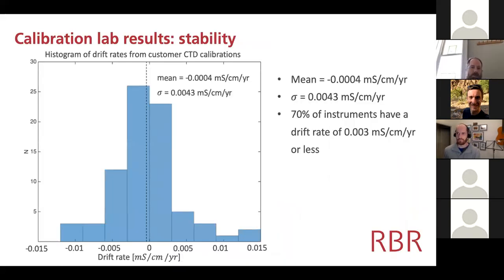Long-term stability. So we took a group of, I don't know, I think it was about 100 instruments maybe. And they had come back from calibration from users who had had them all over the world in completely unknown conditions. We had no idea how long they'd been in the water, under what conditions they were left on the deck, any kind of cleaning or maintenance that was done to them. But we ran a calibration and we assessed it against the last time we had calibrated those instruments. And here are the drift figures we get.